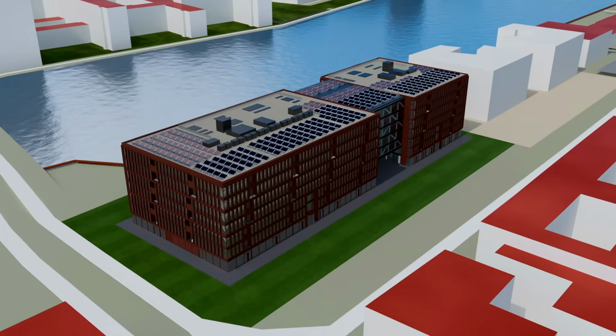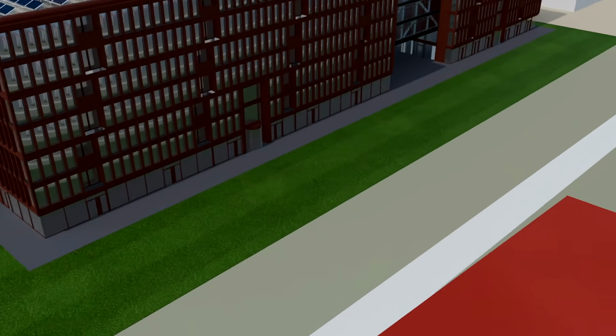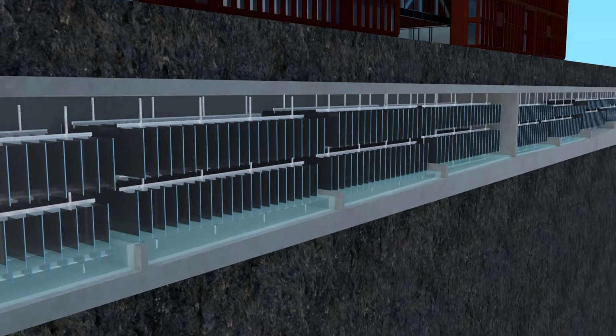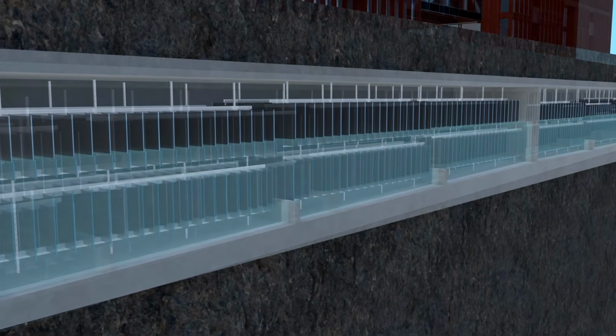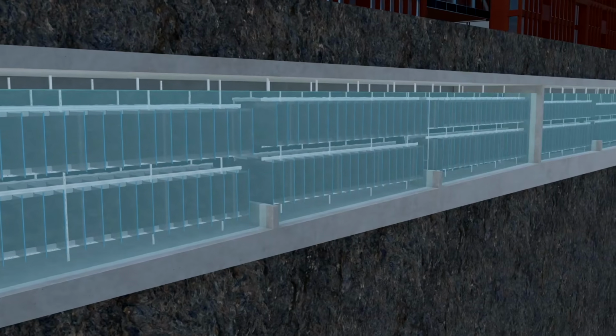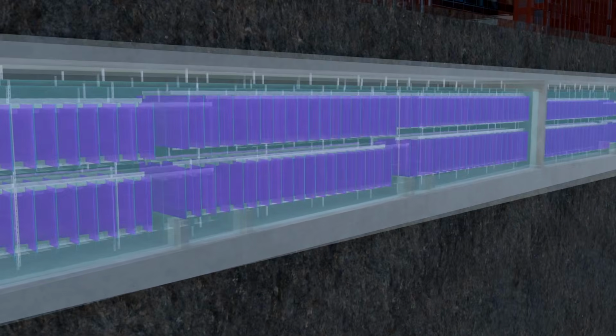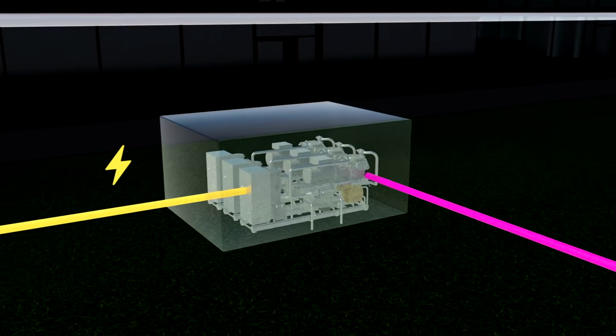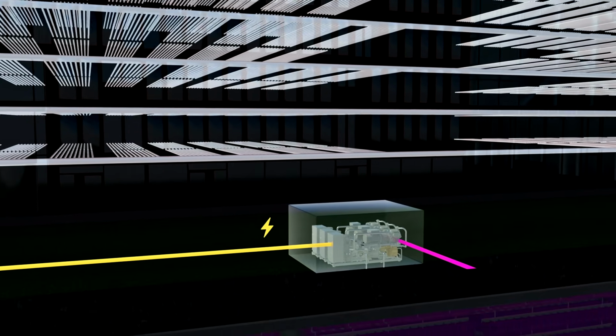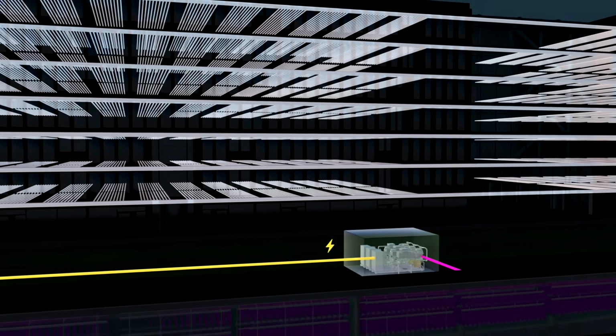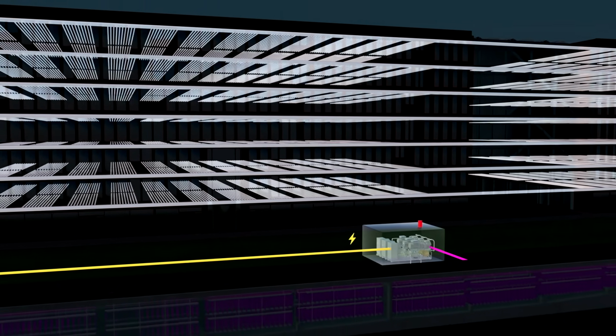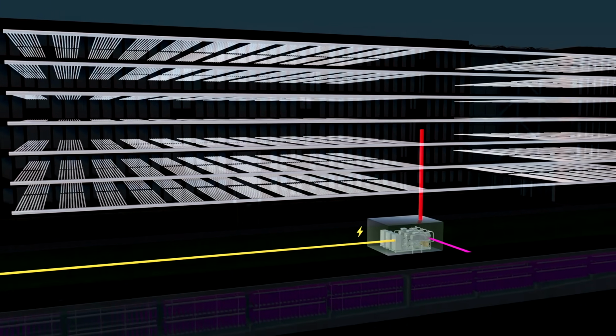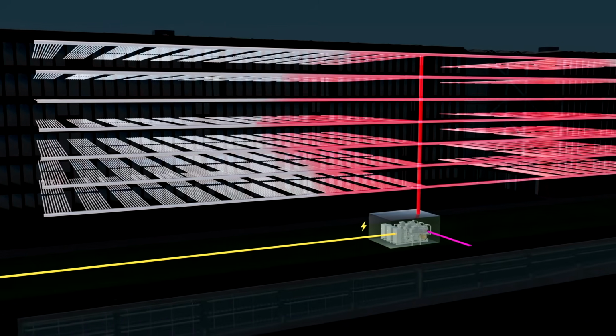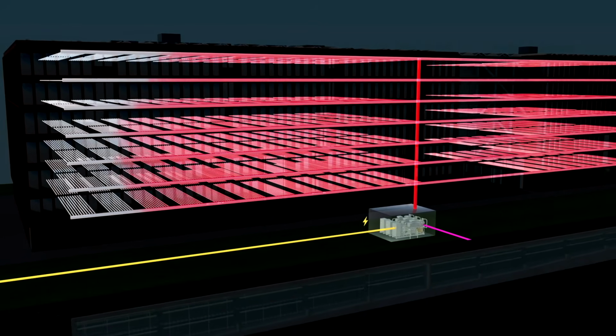The former tunnel has been flooded. Now it serves as a year-round storage reservoir. Summer heat from the building is transferred to the 1,500 cubic meter tank via plate heat exchangers. During the winter, 3 large heat pumps can utilize this reservoir. The building maintains a comfortable temperature through so-called radiant ceiling panels in the offices, as well as additional heat exchangers. In the process, the storage tank cools down.